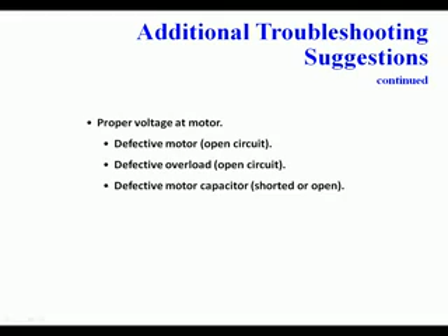If you have no power or low voltage, look for a defective sequence switch. Look for an open thermostat. You might have low line voltage, low transformer output, or the motor's not operating. Look for a defective capacitor or defective internal overload. If you have proper voltage at the motor, a defective overload or defective motor capacitor should all be checked.